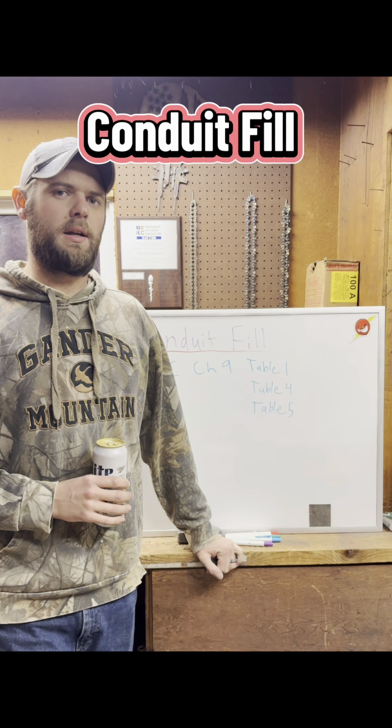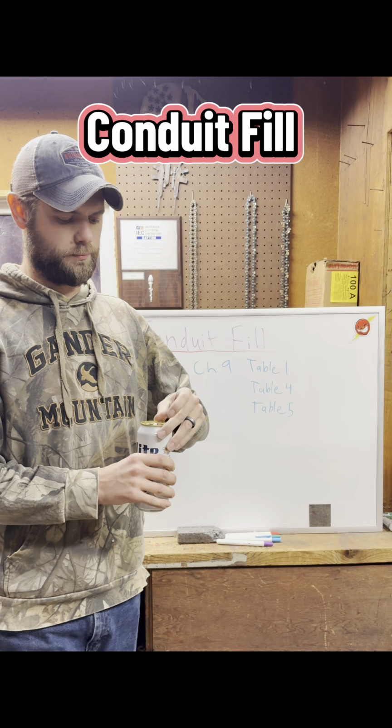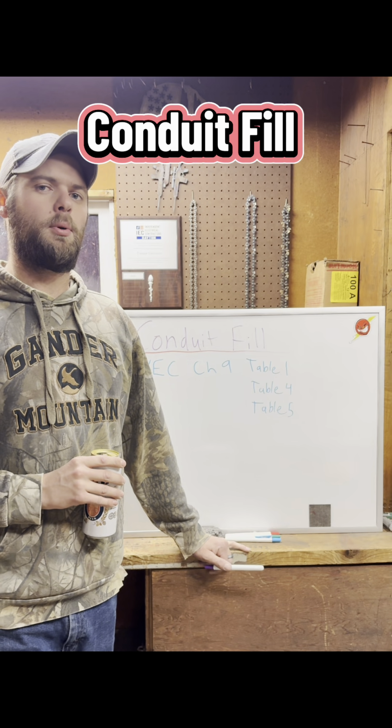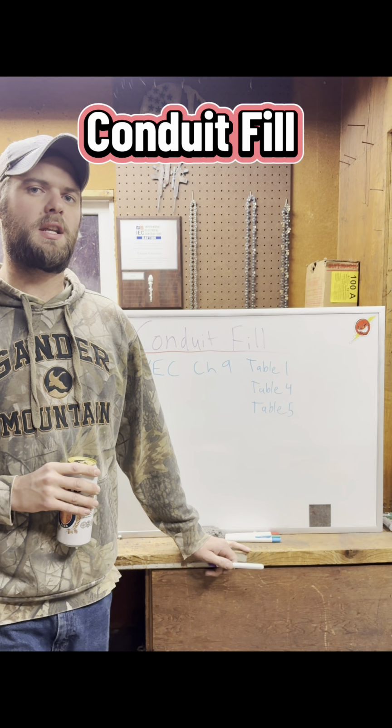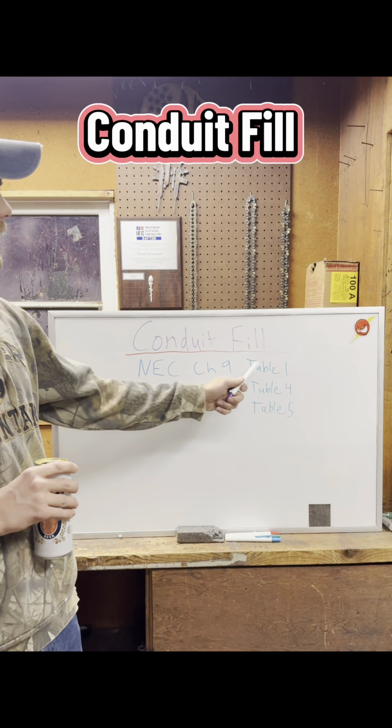All right, let's talk about conduit fill. So check this out. The number of conductors you're allowed to pull in a conduit, not taking ampacity corrections into consideration, is going to be covered by NEC Chapter 9, Table 1. So if you open up your code books and take a look at Chapter 9, Table 1, you'll notice that the overwhelming majority of the time, you're only allowed to fill up a conduit to 40%.